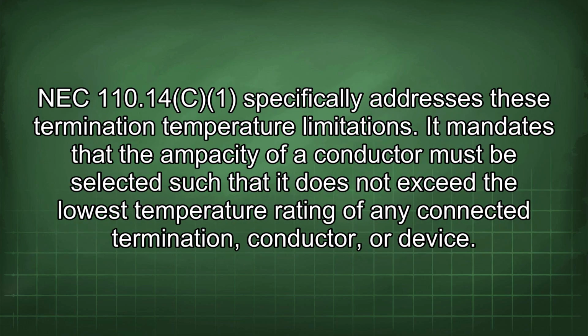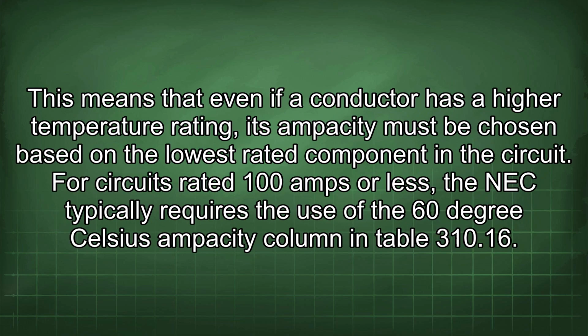NEC 110.14(C) specifically addresses these termination temperature limitations. It mandates that the ampacity of a conductor must be selected such that it does not exceed the lowest temperature rating of any connected termination, conductor, or device. This means that even if a conductor has a high temperature rating, its ampacity must be chosen based on the lowest rated component in the circuit.